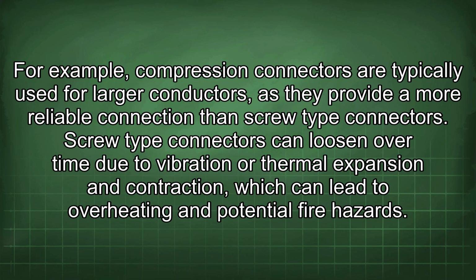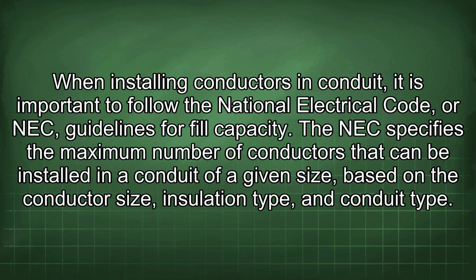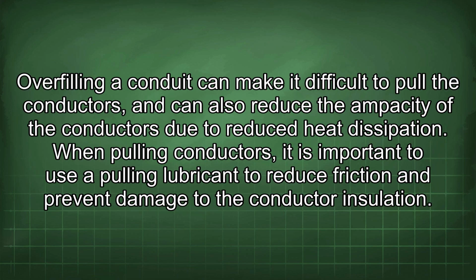Screw-type connectors can loosen over time due to vibration or thermal expansion and contraction, which can lead to overheating and potential fire hazards. When installing conductors in conduit, it is important to follow the National Electrical Code, or NEC, guidelines for fill capacity. The NEC specifies the maximum number of conductors that can be installed in a conduit of a given size based on the conductor size, insulation type, and conduit type. Overfilling a conduit can make it difficult to pull the conductors, and can also reduce the ampacity of the conductors due to reduced heat dissipation.